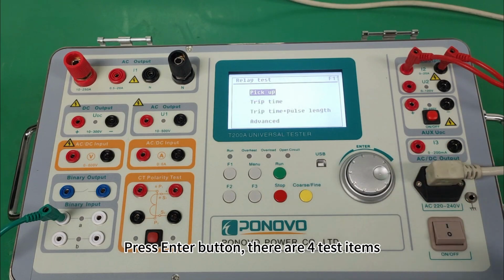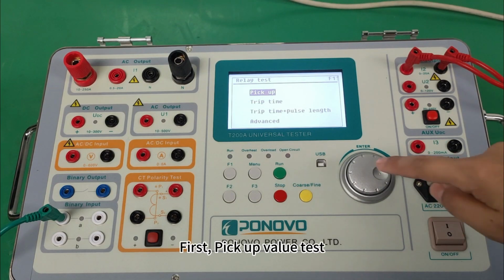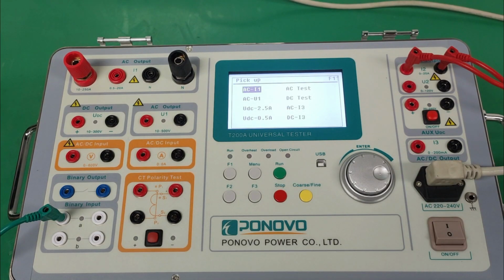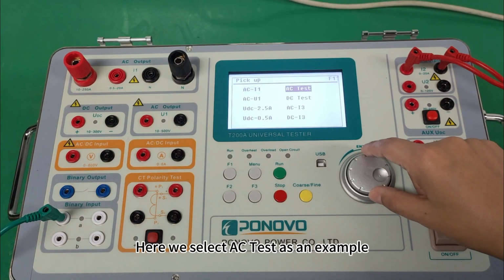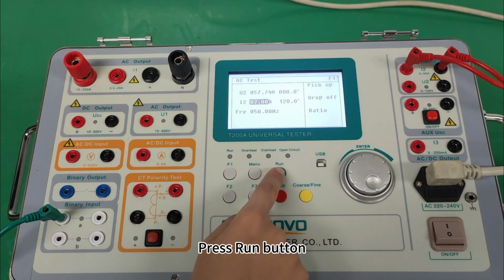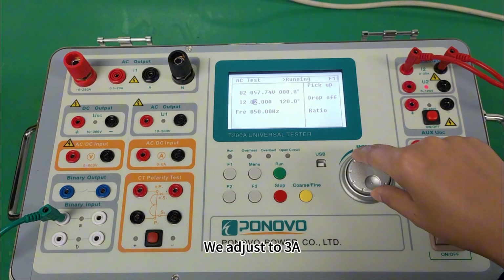Press Enter button. There are 4 test items. First, pickup value test. There are 8 channels for selection. Here we select AC test as an example. We set I2 channel 2 ampere. Press Run button. We adjust to 3 ampere.